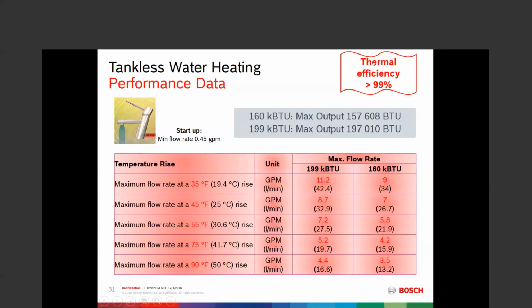And then we got this little flag up here in the upper right-hand corner, and probably some of your eyes are rolling back in your head going, nothing is greater than 99% efficient. It just can't happen. And if it does, it's under special circumstances of a certain precise flow rate and a certain precise temperature rise and all those kind of things. Anecdotally, I have seen at this point hundreds of these units in the field over dozens and dozens of different locations, and consistently, in my mind, how you can be certain, even without an analyzer or anything, that these things are that efficient is I can tell you the temperature of the stack, the exhaust temperature at any installation without even having the unit installed.